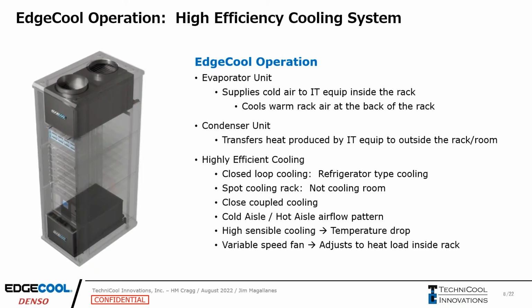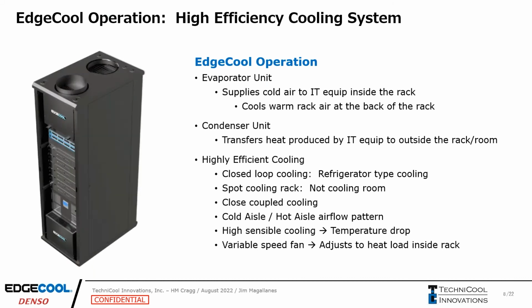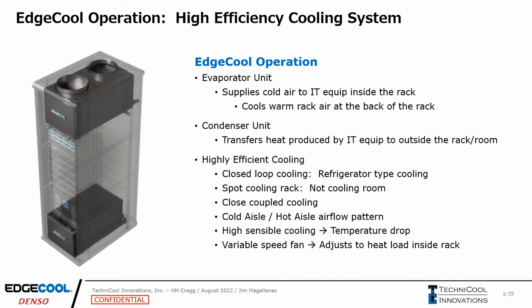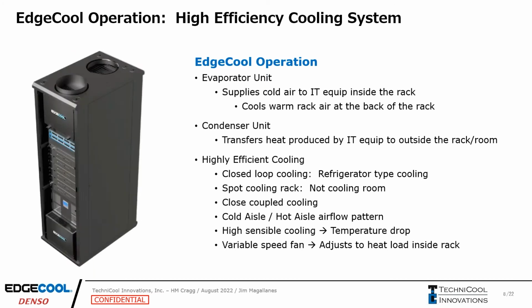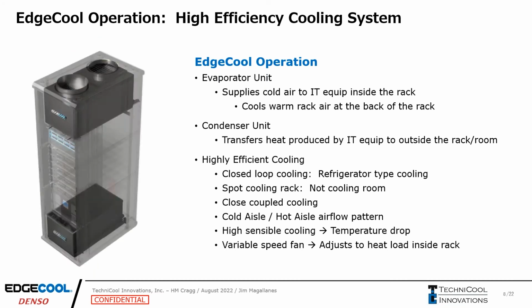And then high sensible cooling. Sensible cooling is temperature drops. Our systems are designed to produce as much sensible cooling as possible, whereas maybe a mini split system, they're more for comfort cooling, meaning that they're designed to cool down people. And a lot of their cooling is broken down into latent cooling, which is actually removing moisture from the air, and that helps people cool down. Not as much as sensible cooling for IT equipment. So IT equipment really needs that high temperature drop, and so that's what we're bringing with our EdgeCool air conditioner.